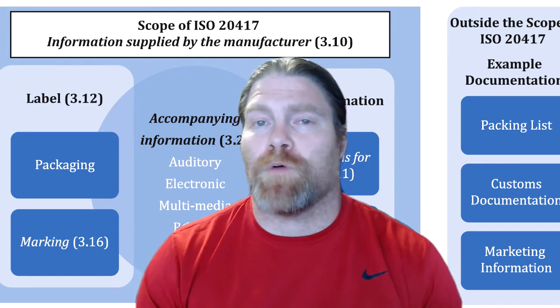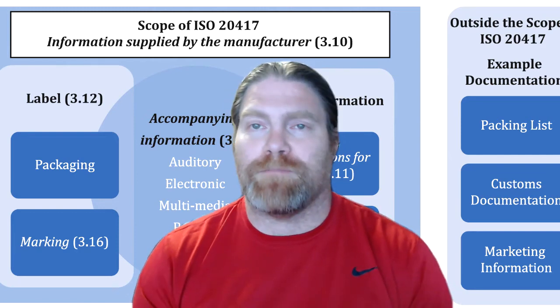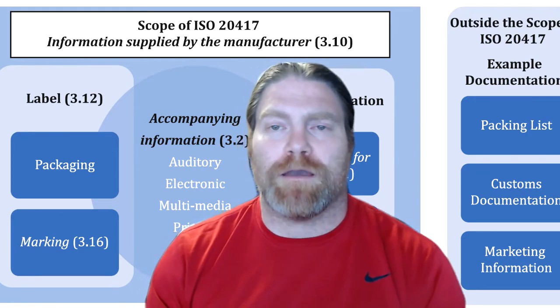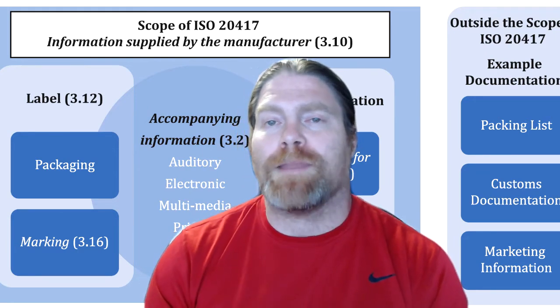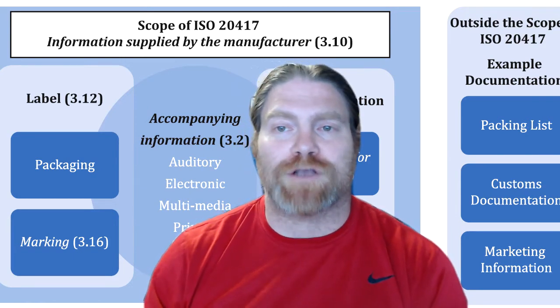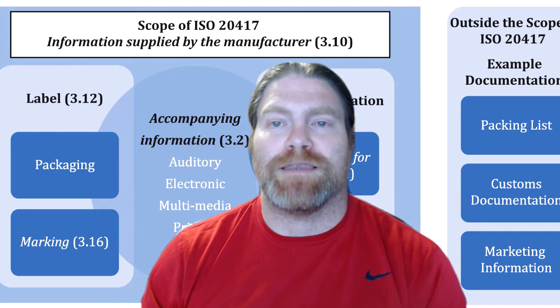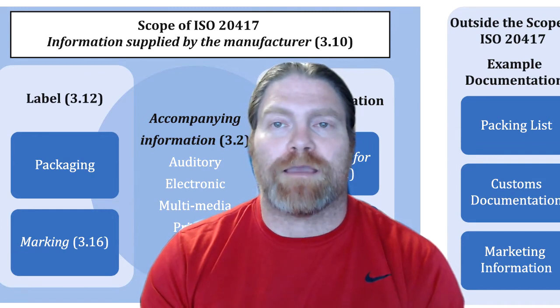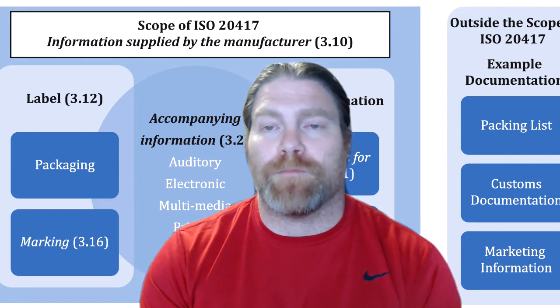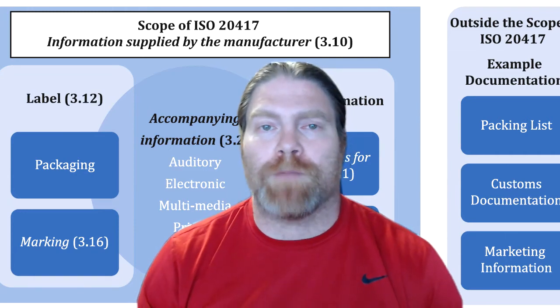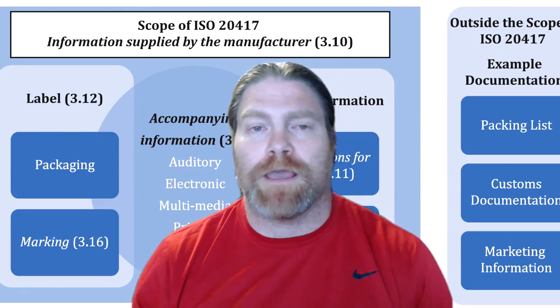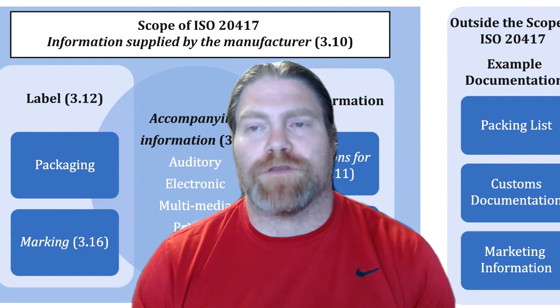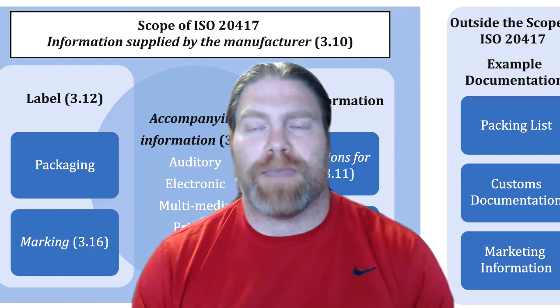So that's our recommendation on how to update your labeling procedure so it meets the requirements of the new MDR. You might ask, what other requirements do I need to comply with the MDR that might need to be in my labeling procedure? Well, if you look at GSPR 23.1, there's a requirement that any information provided by the manufacturer to patients or users also needs to be provided on your website. The easiest way to comply with that is to make your instructions for use downloadable from your website. A lot of companies don't like that — they don't want to make their instructions for use easy for anybody to download, including their competitors. But because everybody has to do it, that levels the playing field.